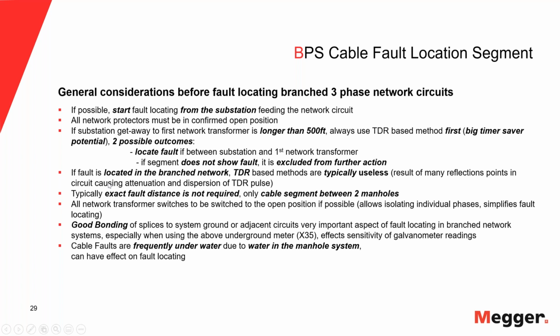I just talked to a customer a couple of months ago, and they used to do that all the time, which made their fault locating very efficient, but at the expense of the time to make sure that the transformers were in an open position. And because they had a fairly old system, they had to basically go to every transformer and manually check that this happened.